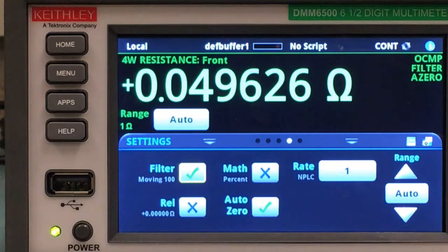Let's return to the home screen. Now you see we have a very smooth output of what we are trying to measure, which is our device under test of 50 milliohms. Notice that we are within the one percent limit, so just above the 49.5 milliohms lower limit.